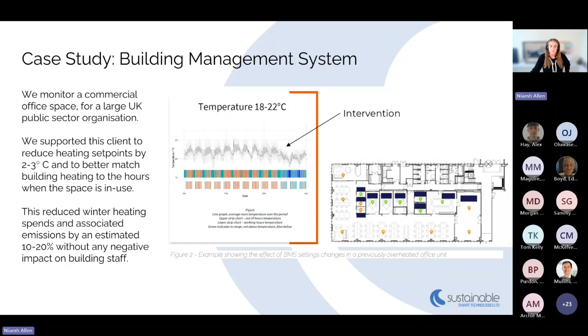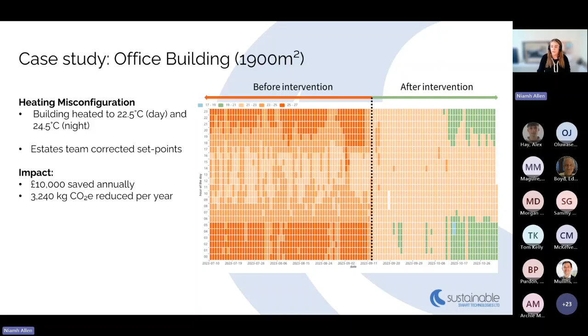Very quickly, this is one building we identified - you can see on the left-hand side is before, whilst we were monitoring. The black line is where we had a Teams meeting with the client, and then you can see after intervention. The building was being heated at 22.5 degrees during the day, and at night time going up to 24.5 degrees, 24/7, 365 days a year, so it was being overheated. We saved them £10,000 for that site straight away, just from one conversation saying you need to adjust your BMS settings. We weren't doing an integration project for this, we just told them and they adjusted it.